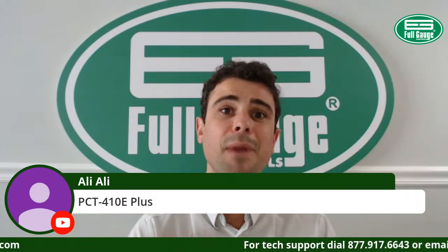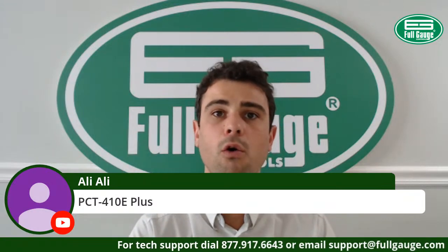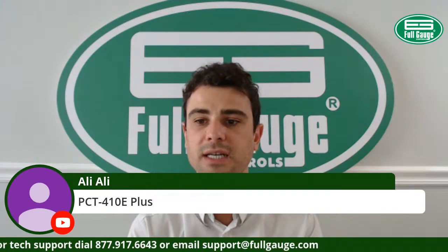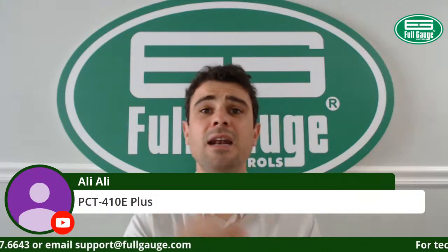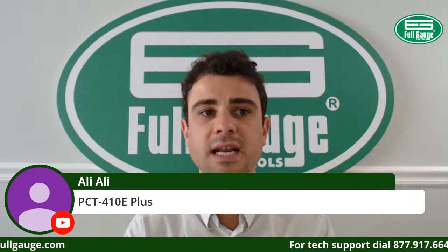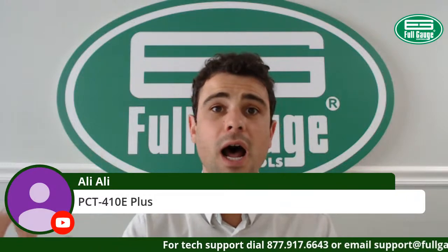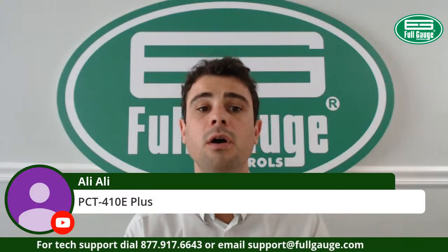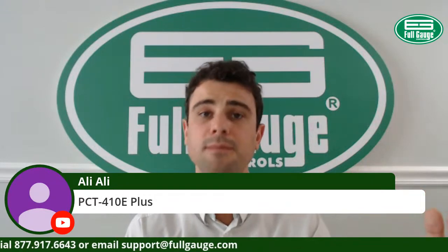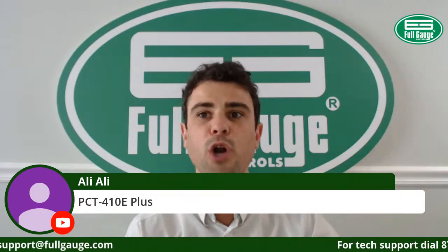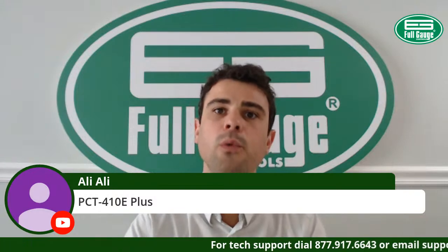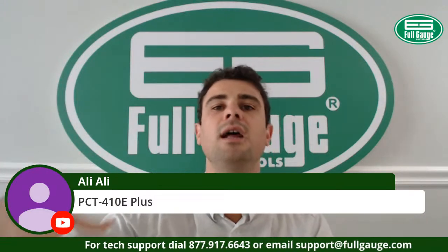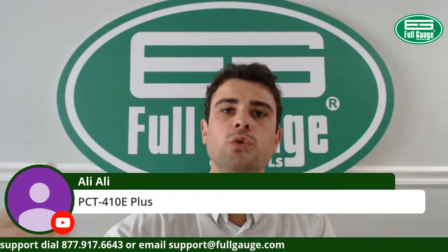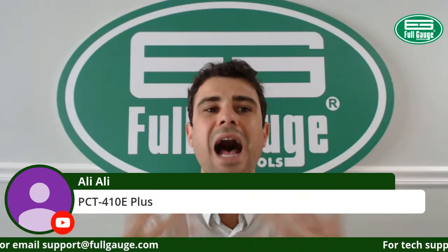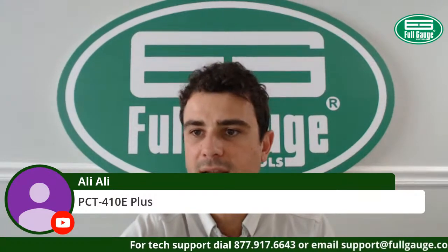I only mentioned one input, only one point of measurement, the discharge pressure. And then we needed to control 4 condensing fans, so 4 outputs are needed for that. So one pressure input will monitor the pressure, and based on the cut in and cut out, will activate the 4 different condenser fans, which will be connected to the controller outputs. And the answer is PCT 410E.